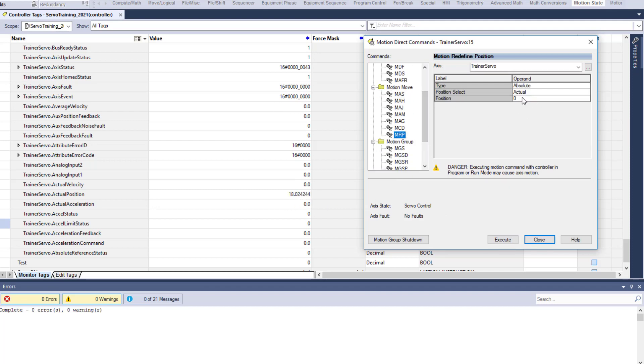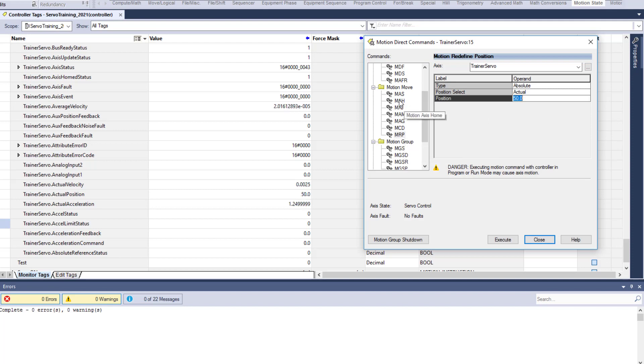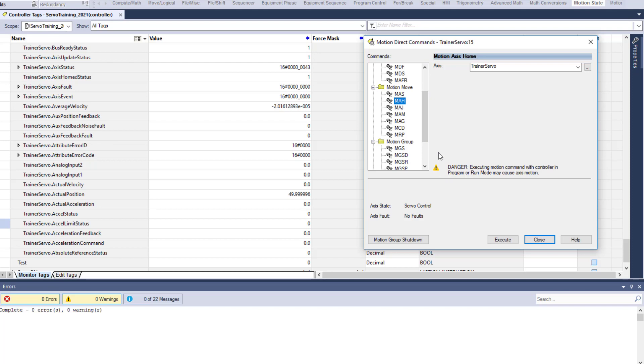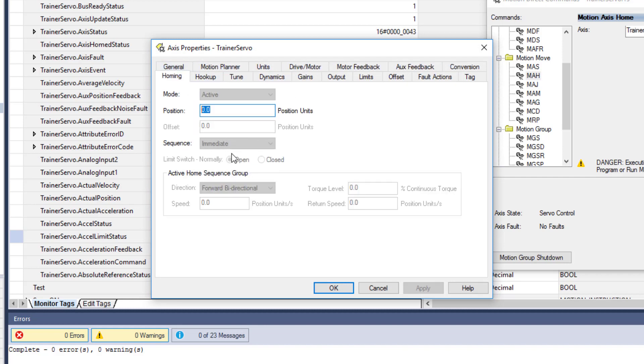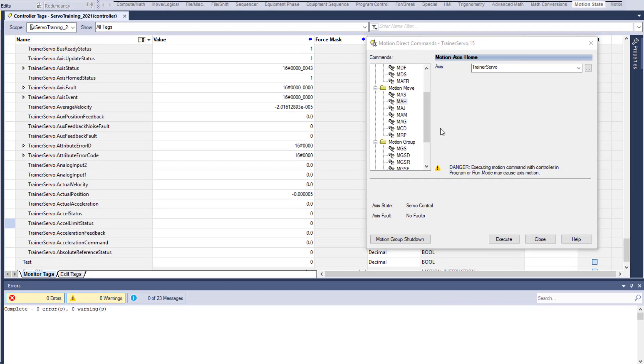What if you want to redefine the position? You can redefine the position — say this is actually a position of 50. Come in here, redefine it, and it goes to a position of 50. I always recommend if you're homing, and you're at zero, always go to home and home it there. Your home could be based on your properties — it doesn't have to be zero. Your home could be set at 50 or whatever the case may be, or it may home to a switch. These are tools you can use to help troubleshoot.